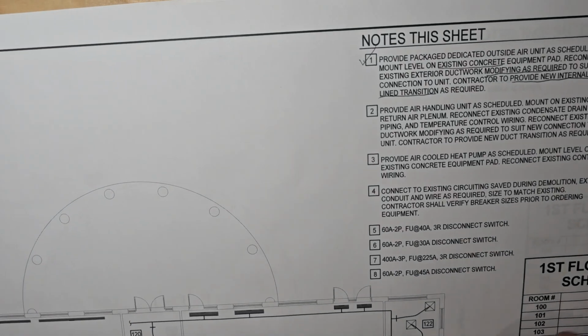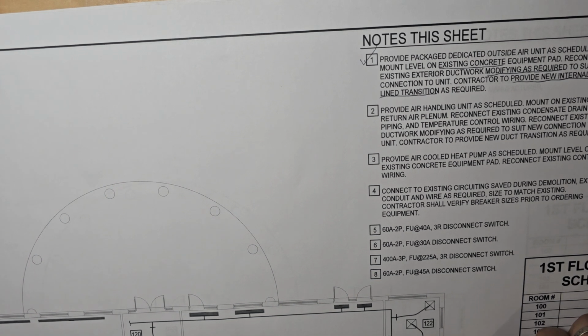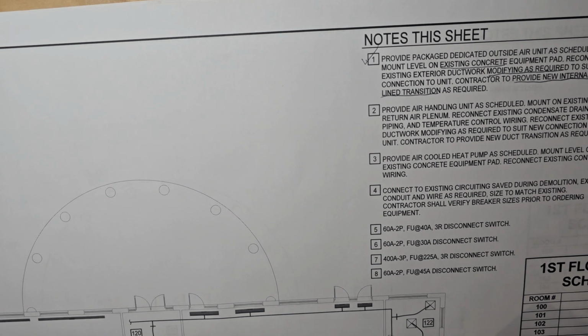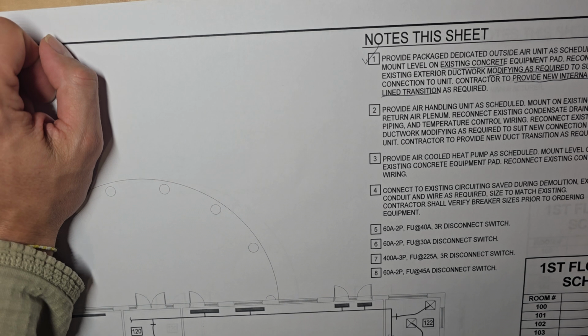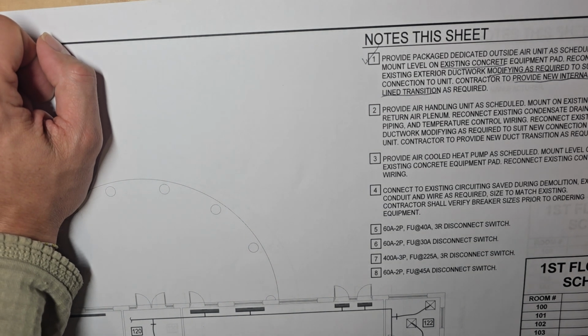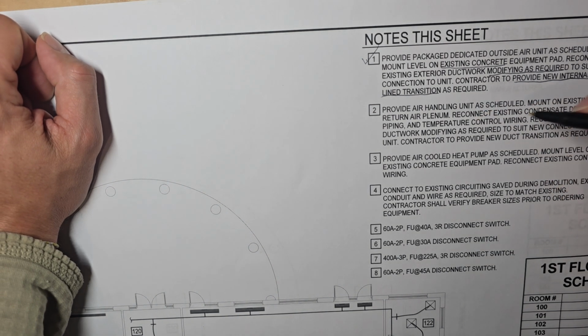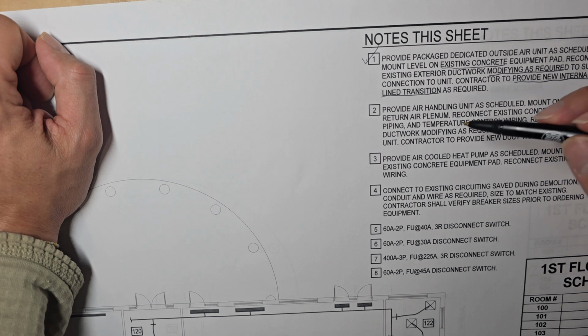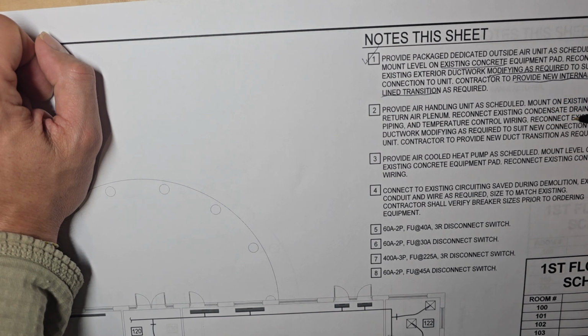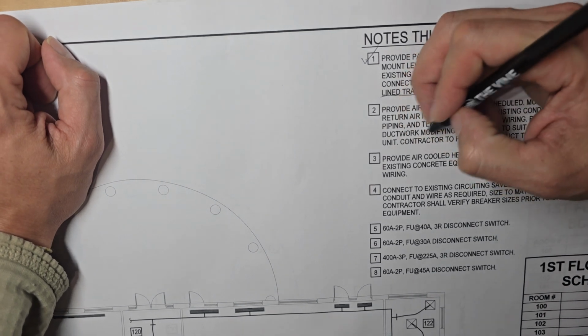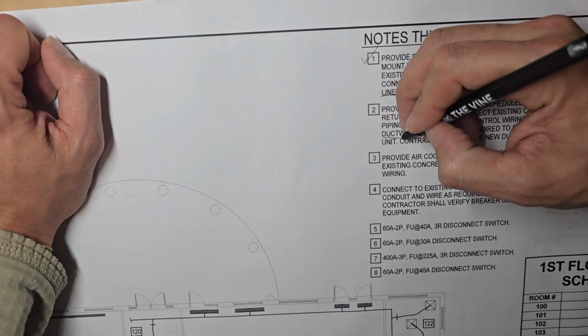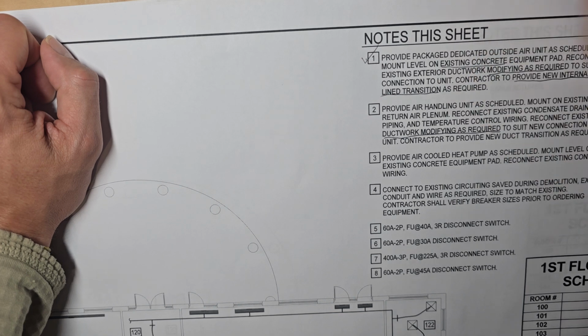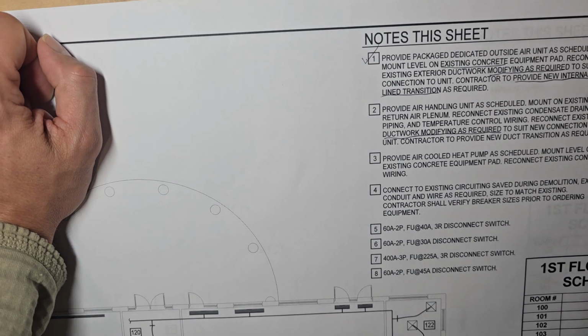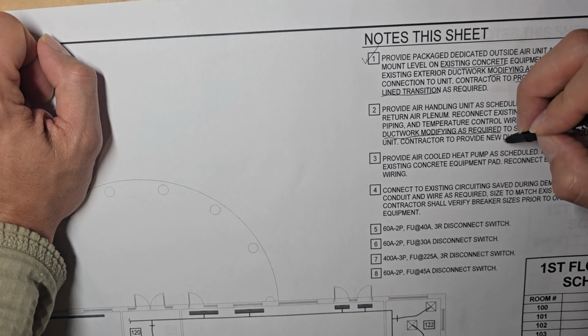All right, number two, provide air handling unit as scheduled. Mount on existing return air plenum. Reconnect existing condensate drain piping and temperature control wiring. Reconnect existing ductwork, modifying as required.